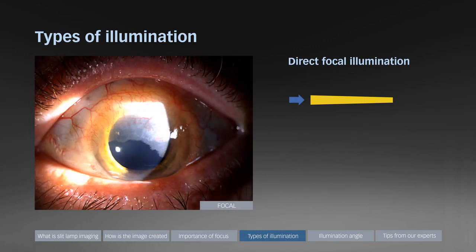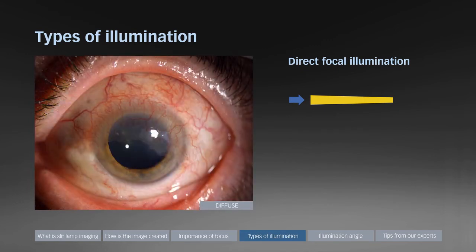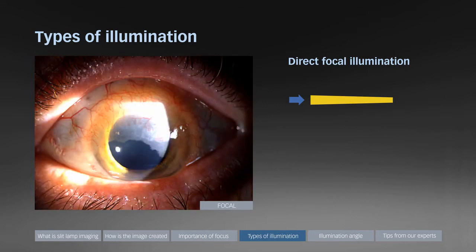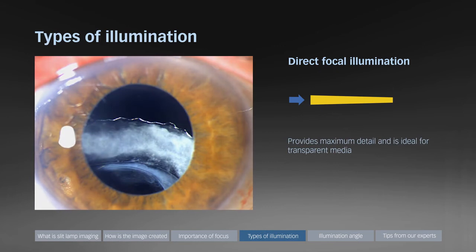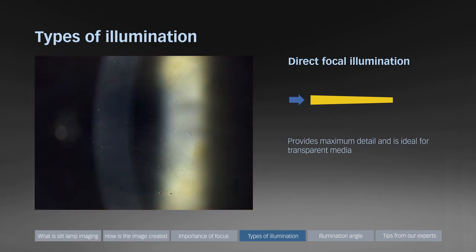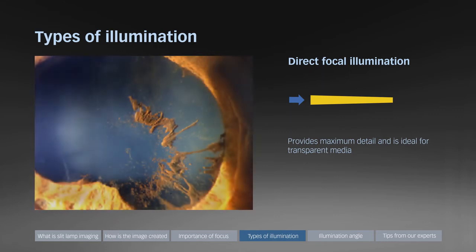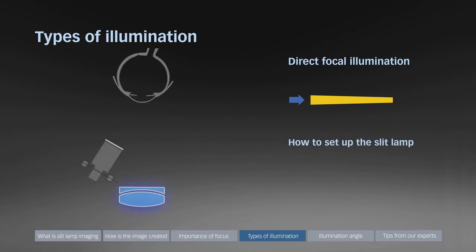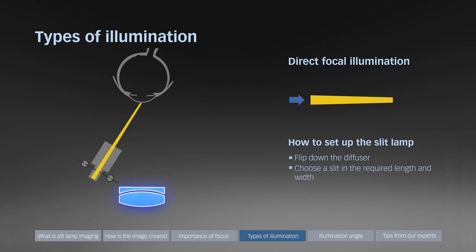Direct focal illumination is a bright focused light. Note how the direct focal illumination enhances the sharpness of the new vessels growing into the cornea. Direct focal illumination increases the contrast and in many cases can make more detail visible. It has the ability to show structure and detail in media that would appear transparent under diffuse illumination. To set up the slit lamp for direct focal illumination, flip down the diffuser, choose a slit in the required length and width, and add a small amount of background illumination if required.